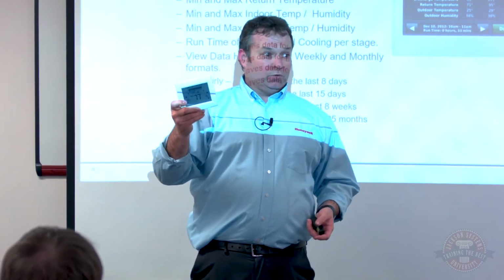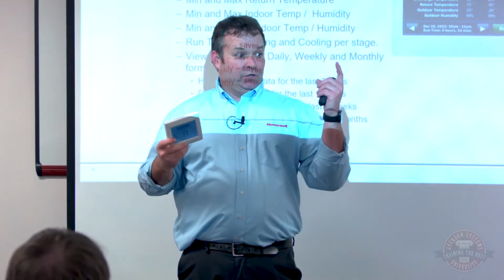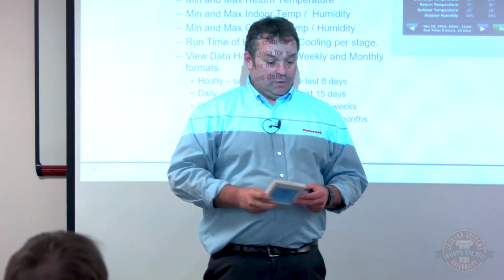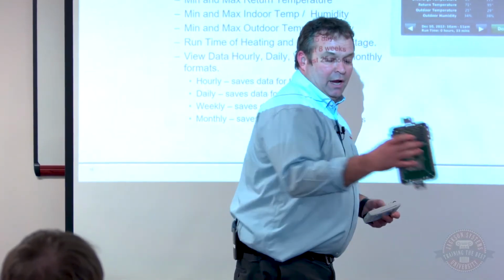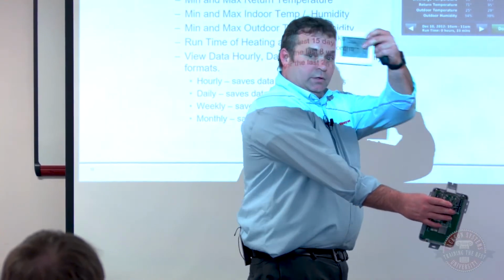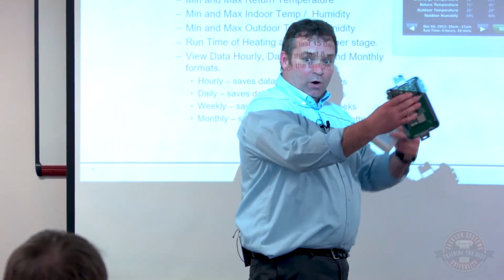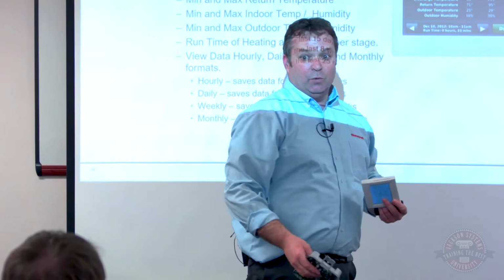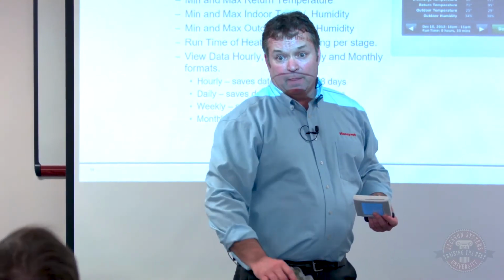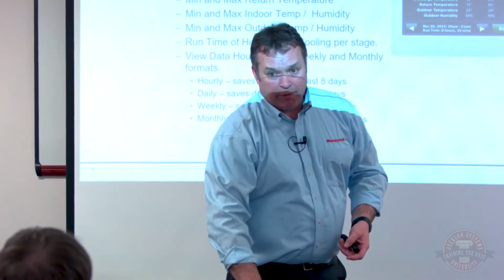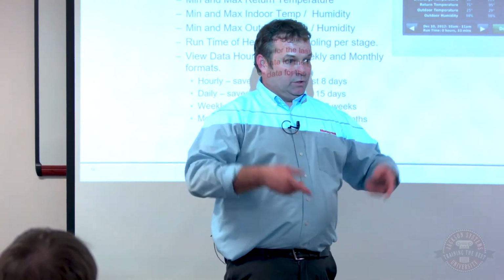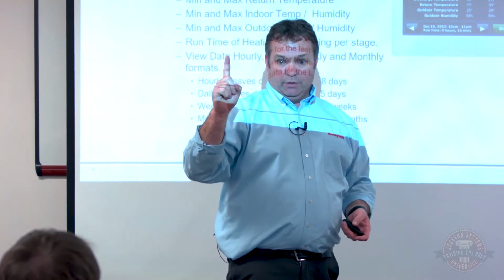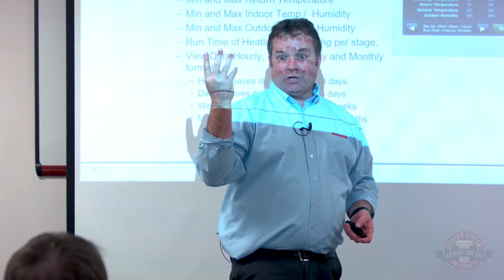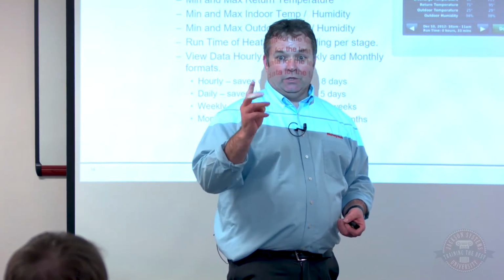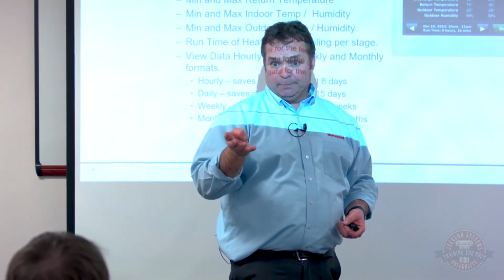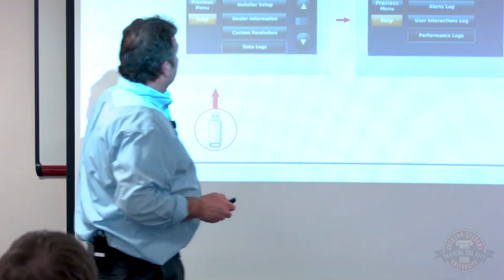So I could have 4 zone systems, 16 thermostats, and use 1 gateway to manage all that. But if I had this EIM hardwired into zone 1, going wireless between here, and I had a hardwired stat and 3 wireless, it would count as 2. So if it's just a 1 zone system, it counts as 1 channel. It's like a 4 channel deal, and I can only use 4 per gateway. All right, let's move through.